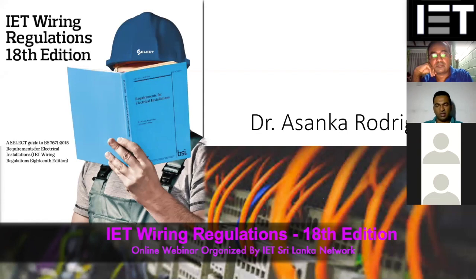There is no restriction. Now in the new standard, there is no restriction on the number of socket outlets; it is restricted by the area and the overcurrent protection. There are 3 overcurrent protection schemes. One is a 32 ampere ring circuit, the other one is a 32 ampere radial circuit, and the third one is a 20 ampere radial circuit. So there is no restriction other than the area restriction.